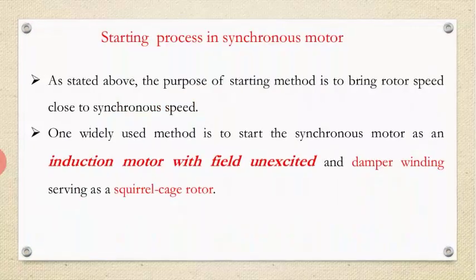Okay, so here, as stated above, the purpose of the starting method is to bring the rotor speed close to the synchronous speed. First we have to bring the speed of the rotor to the synchronous speed. One widely used method is to start the synchronous motor as an induction motor. We start it as an induction motor with the field unexcited and the damper winding serving as a squirrel cage rotor. I have already discussed this point.